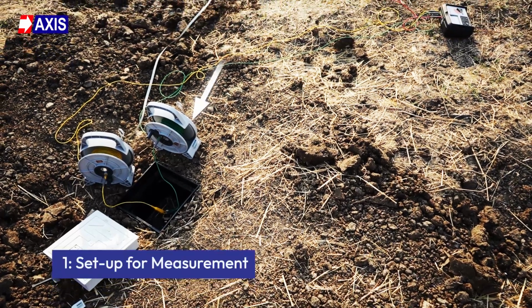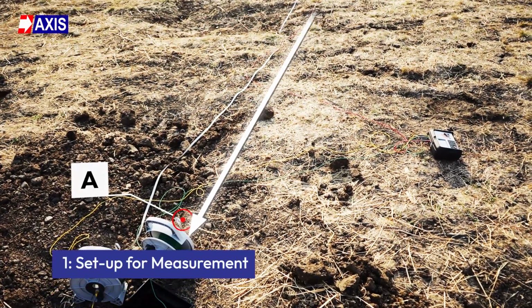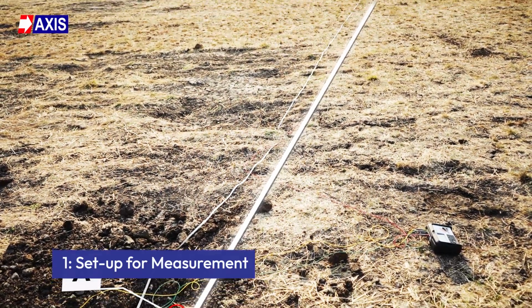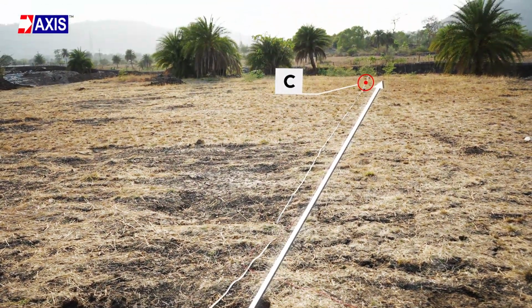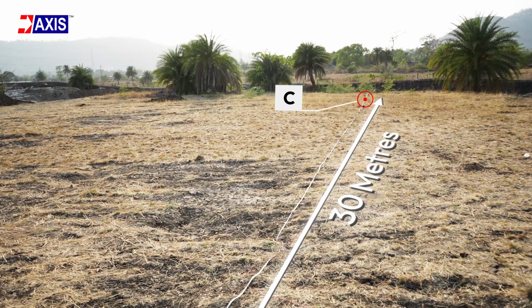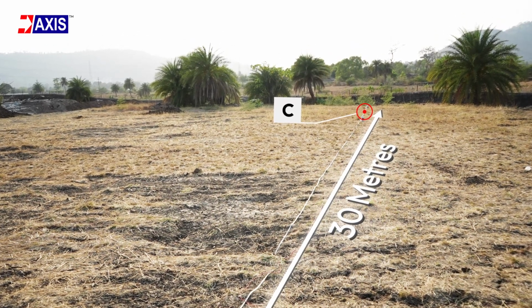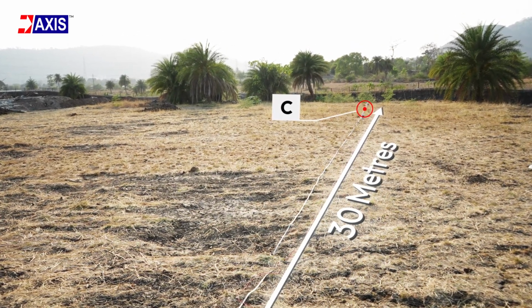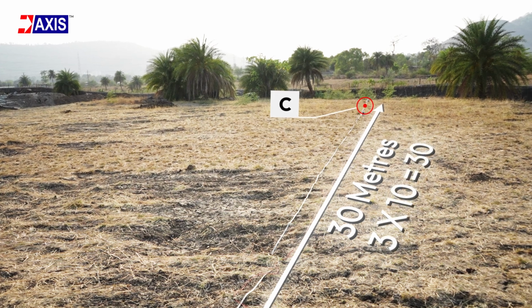Step 1. Set up. Place the current electrode C in a straight line from electrode A. The minimum distance between A and C is 30 meters for a single rod installation. The distance between electrodes A and C should generally be 10 times the length of the earth electrode.